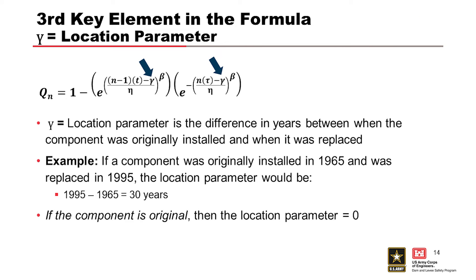Another important parameter, or one of the key parameters in the formula, is the location parameter. Location parameter is the difference in years between when the component was originally installed and when it was replaced. So, an example is, if a component was originally installed in 1965 and replaced in 1995, that location parameter would then be 30 years.